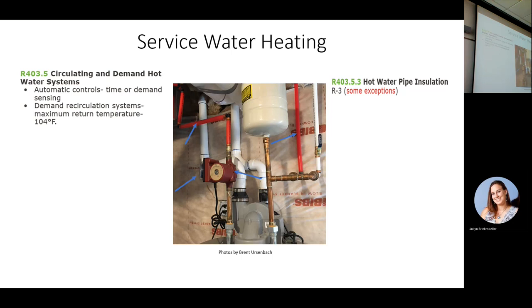But they put the pump in the wrong place. They put it right in the main hot water line. The pump needs to be over here, so it's just pulling it through that loop. Because as it was installed, all the hot water in the whole house that's being used is running through the pump, whether the pump's running or not. And so you're gonna have drop or loss, pressure drop, trying to run past the impeller in the pump.